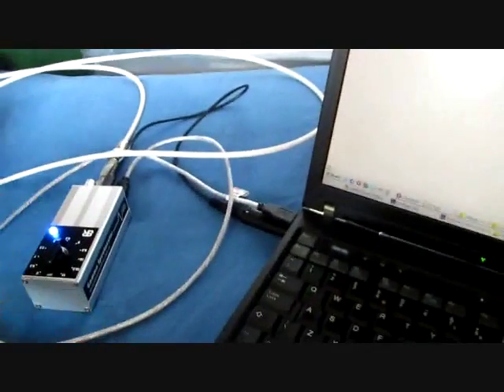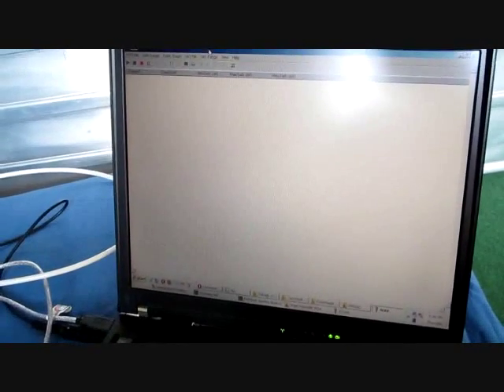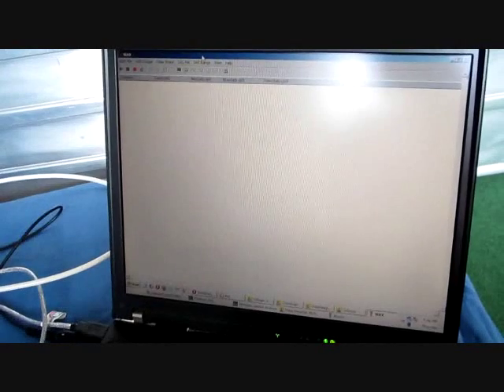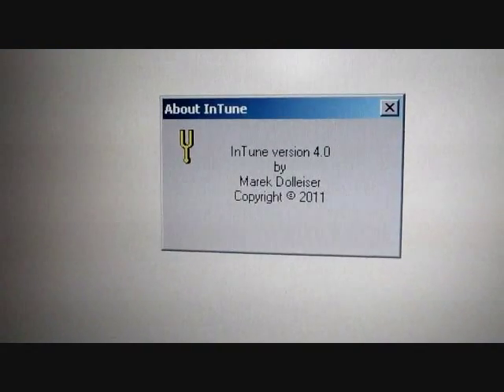Alright, so first of all, as I said, I already determined the proper operating voltage, which is 850 volts for this detector. I left the detector on for about half an hour before I use it, because temperature still messes with the calibration. If you want to do that properly, just let your detector run for a while, and then we can check out the actual pulses with a program called Intune. You can see Intune.